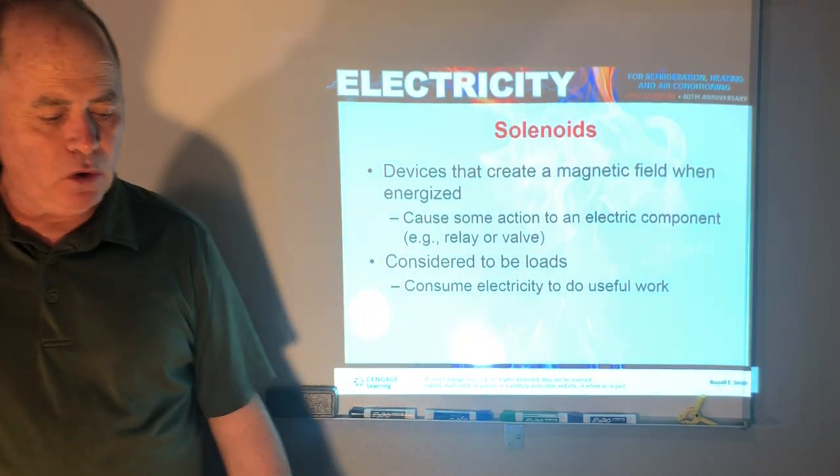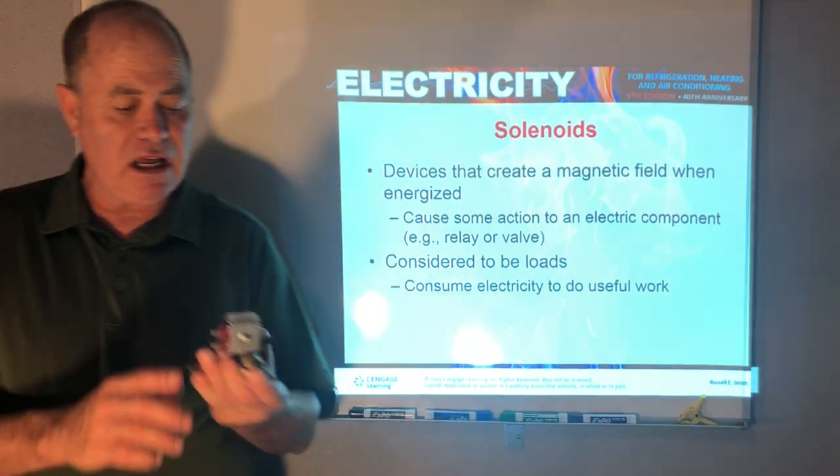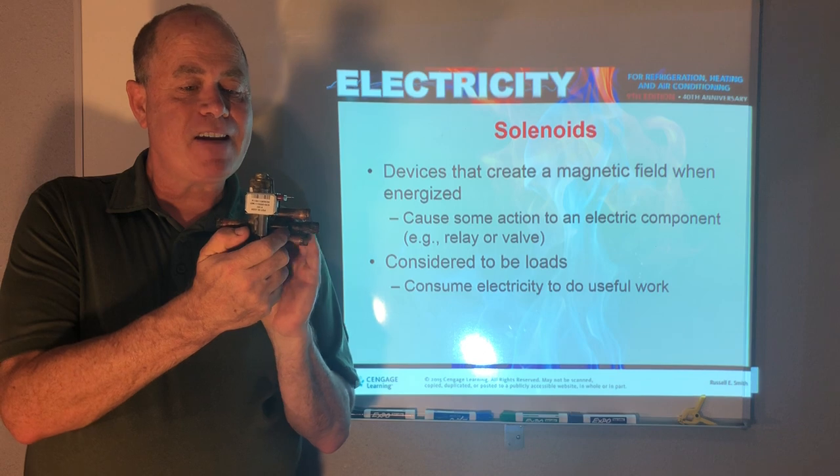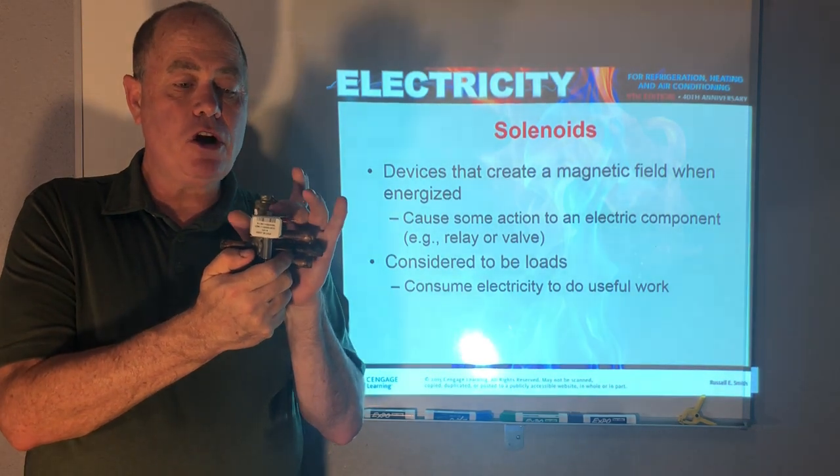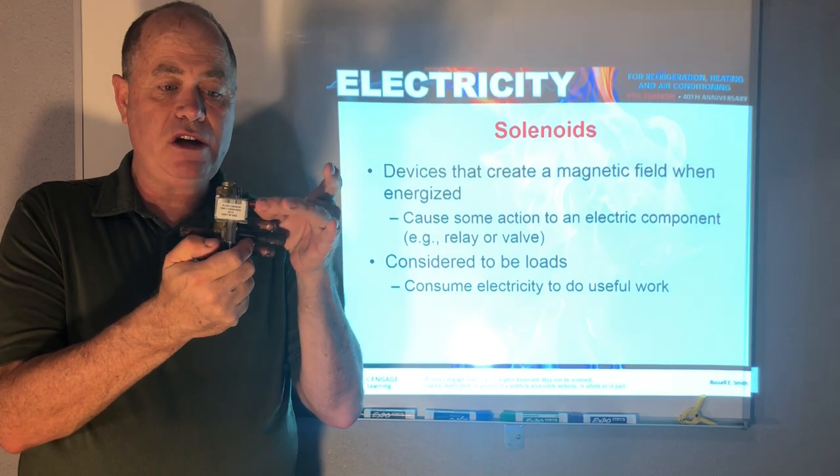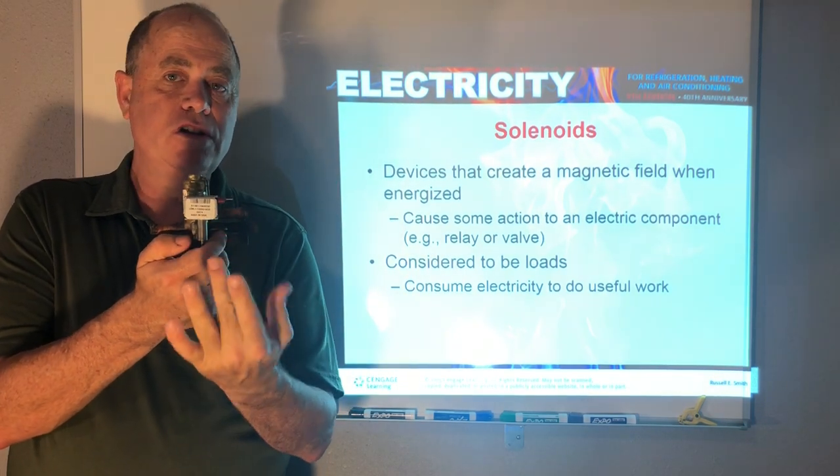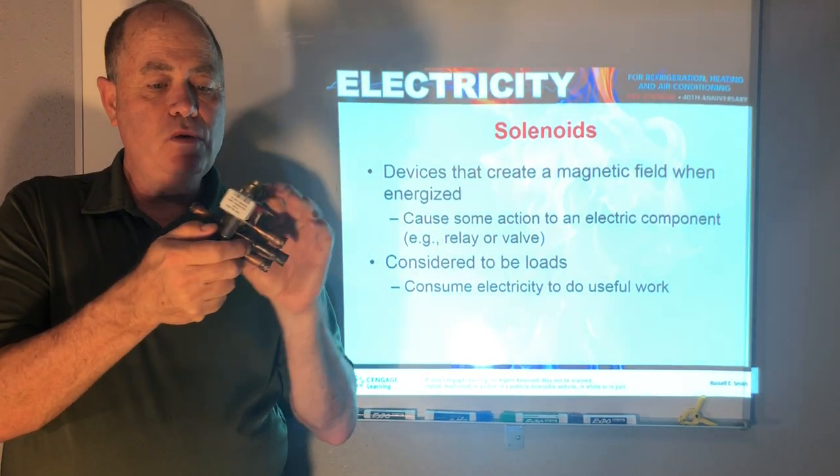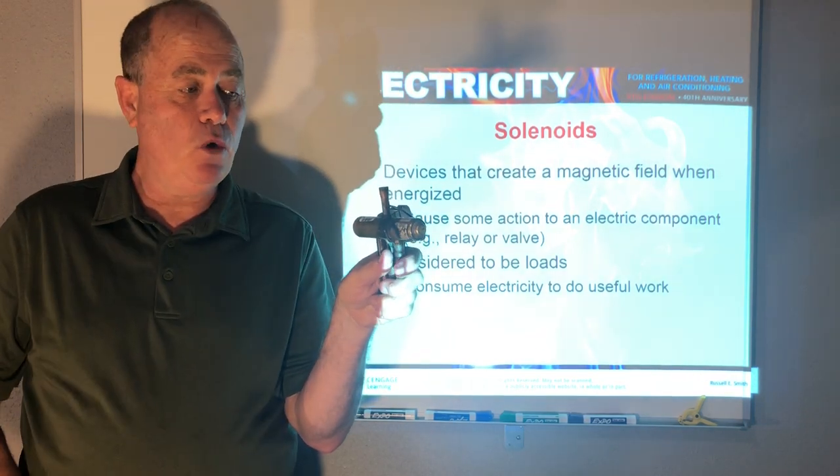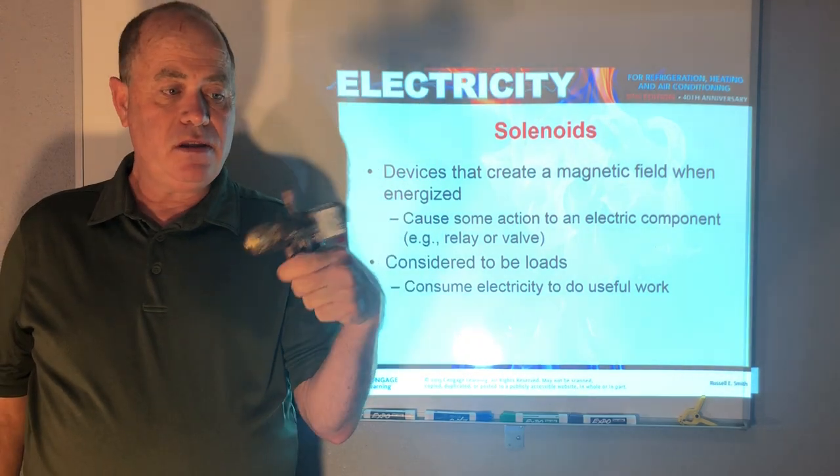Now solenoid coils are quite often used like this solenoid coil for a heat pump. It's called the reversing valve. And this is the solenoid coil. And when we energize this, a magnetic field will be created and will shift this inside to allow the refrigerant to flow in one direction or the other.